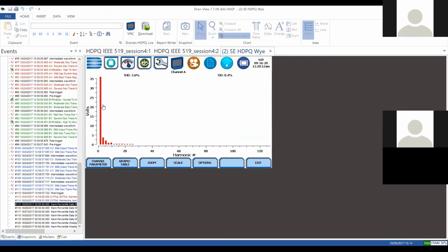Okay, we are a light to medium manufacturing facility where we build all our products. So here's just a live feed. This is from a real instrument. You can see here's the THD up at top at 3.6%. And this is channel A. I can easily just go change the channels.